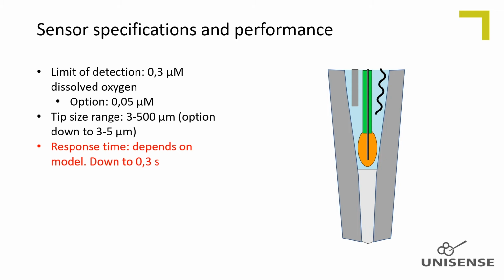The response time is a function of the oxygen diffusion path length into the working electrode and is chosen to obtain the best compromise between sensitivity, response time and stirring sensitivity. Small sensors are made with shorter response time than larger, but all have below 10-second response times. Details on response times are found in the oxygen sensor specification on our website. Oxygen sensors can be custom made with short membranes to shorten the diffusion distance, and thus oxygen sensors can be made very fast, down to 0.3 seconds for a 90% response time.